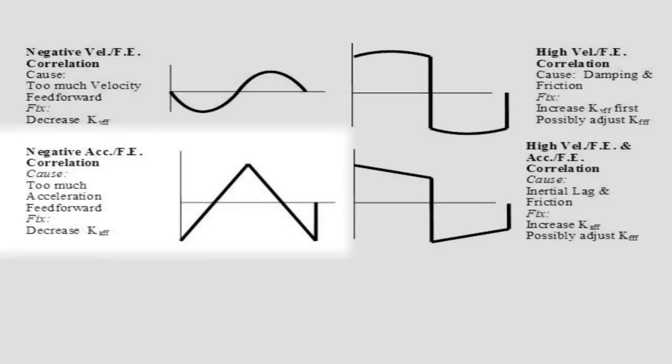The bottom left corner shows a response that is the opposite from the diagram in the bottom left corner of the previous slide. This shape is due to having too much kAFF, so to correct it, just decrease kAFF until the triangular tips on the left and right come up to zero, the tip in the middle comes down to zero, and the following error oscillates about zero.